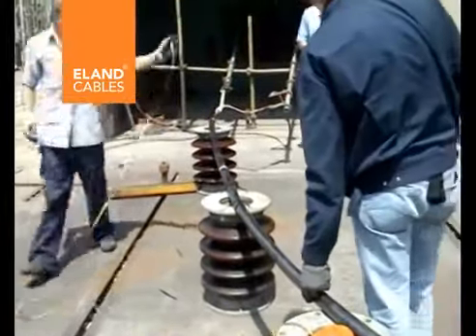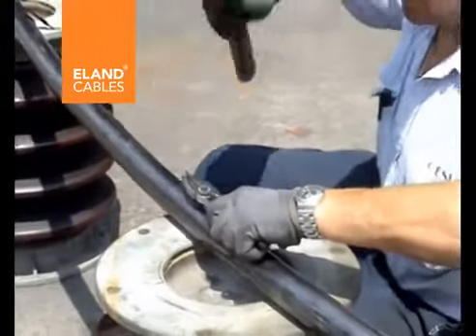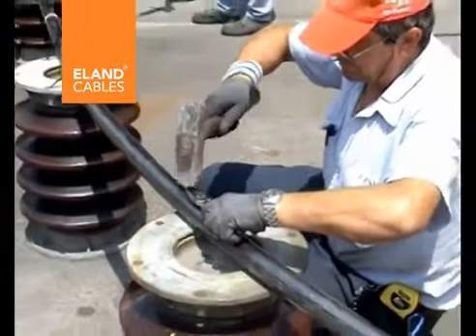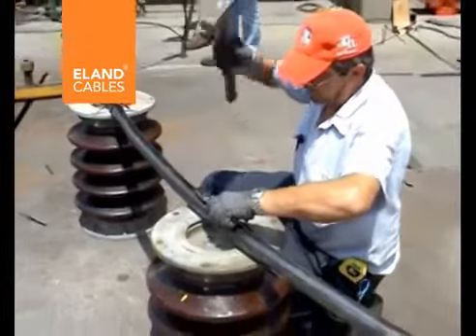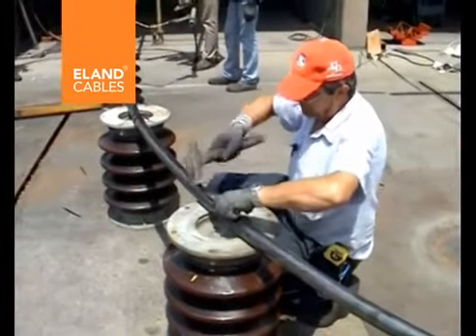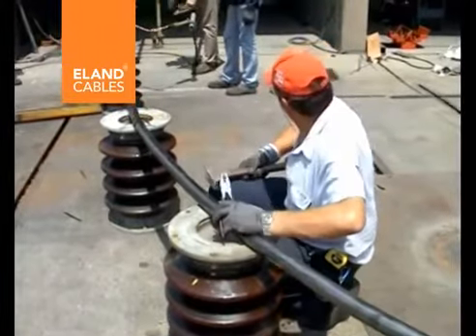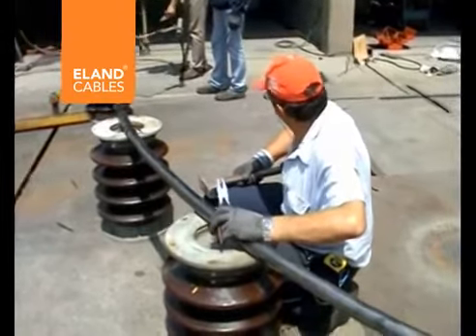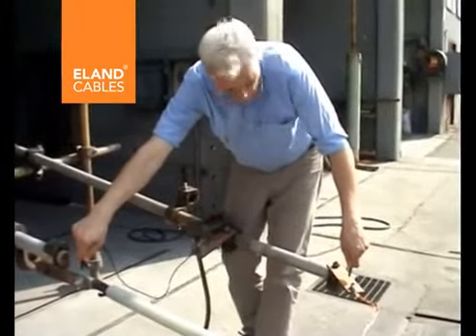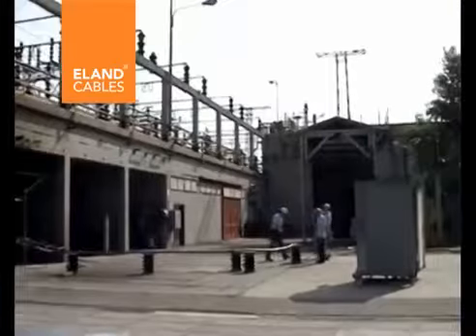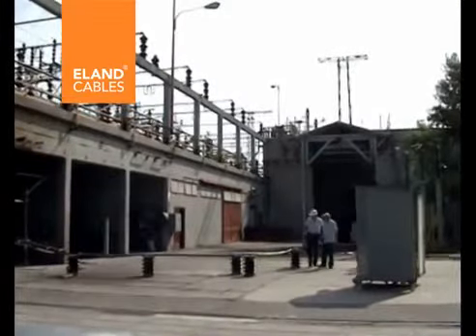With the connections made, a spike of the prescribed diameter was driven into the center of the cable sample to ensure contact with both the copper wire screen and with the phase conductor. Once verification of the short circuit between the copper wire screen and the phase conductor was confirmed, the cable was then declared ready for testing, and the team withdrew to the safety of the observation bunker.